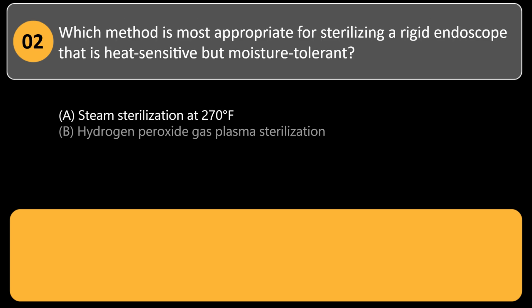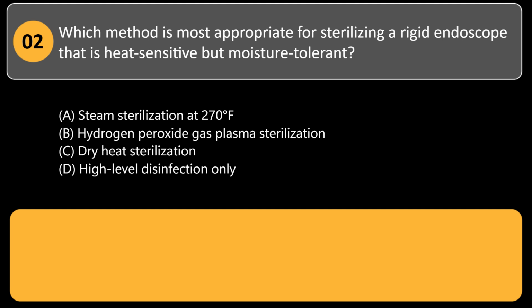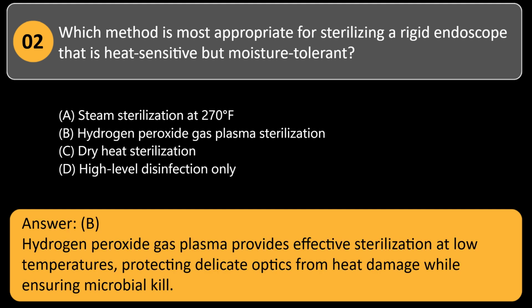Which method is most appropriate for sterilizing a rigid endoscope that is heat-sensitive but moisture-tolerant? A. Steam sterilization at 270 degrees Fahrenheit. B. Hydrogen peroxide gas plasma sterilization. C. Dry heat sterilization. D. High-level disinfection only. Answer: B. Hydrogen peroxide gas plasma provides effective sterilization at low temperatures, protecting delicate optics from heat damage while ensuring microbial kill.